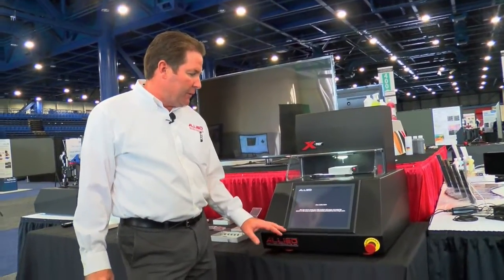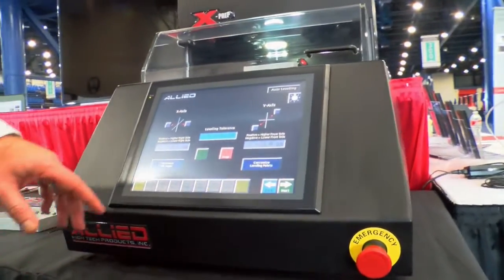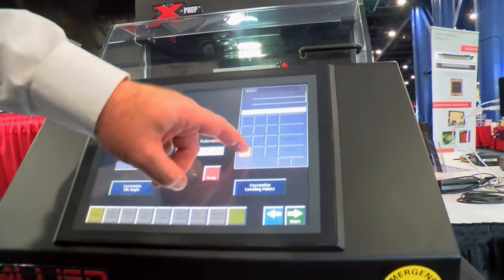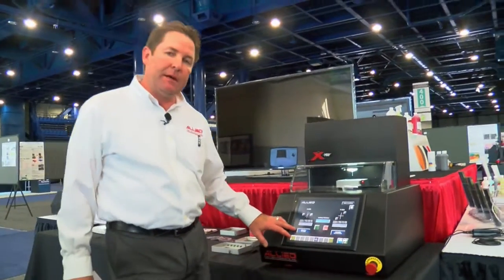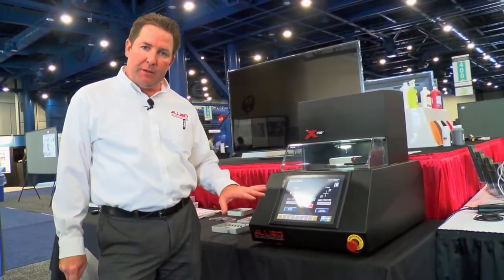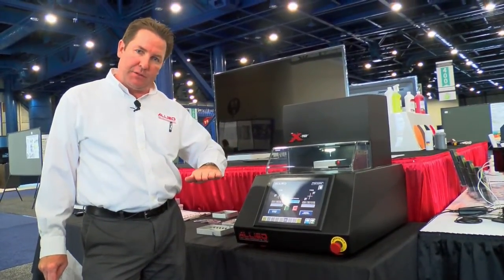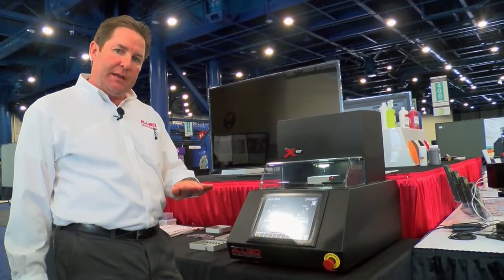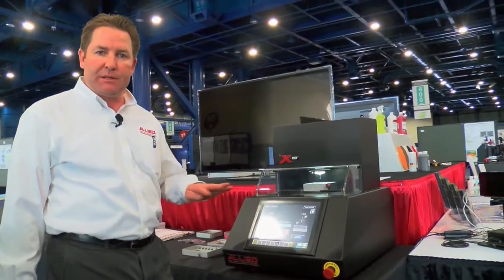One of the other features of this tool is automatic leveling capability. You can set a leveling tolerance for three-point leveling down to as low as half a micron, with numeric value entry. This also has the ability to set a customized tilt angle, so if you have an object that is not visible as you arrive through various layers, you can change the leveling of the sample accordingly. We also have custom leveling points where you can set these points to different locations.